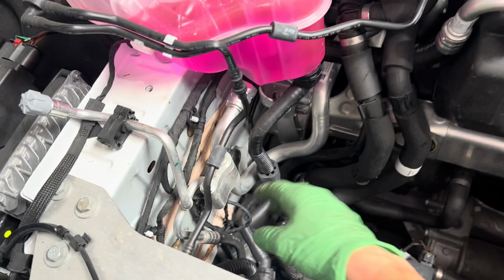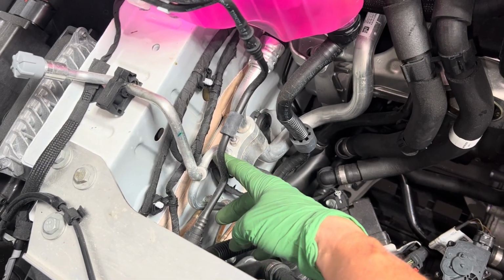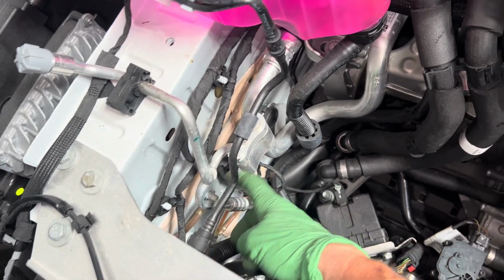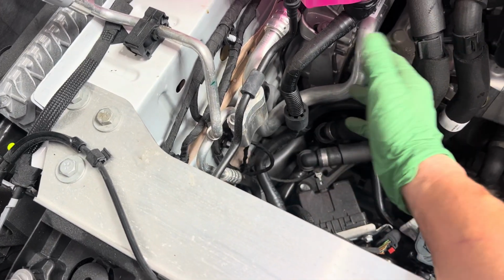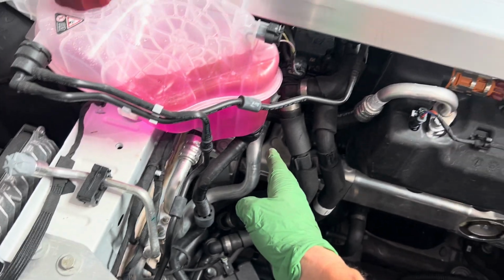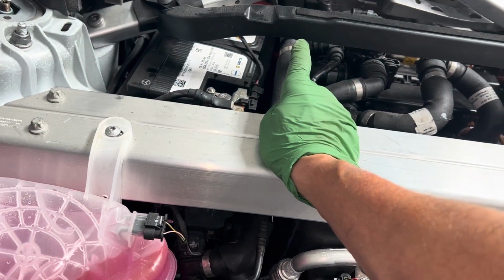But they're making it do one more job. They're doing extra subcooling, picking up the heat out of the liquid refrigerant, even making it colder, giving it a higher BTU capacity before it delivers it to the expansion valve.